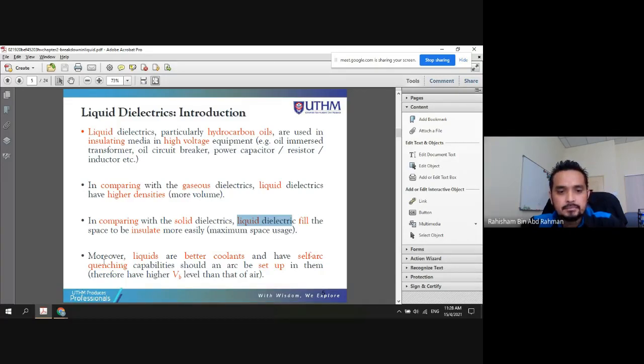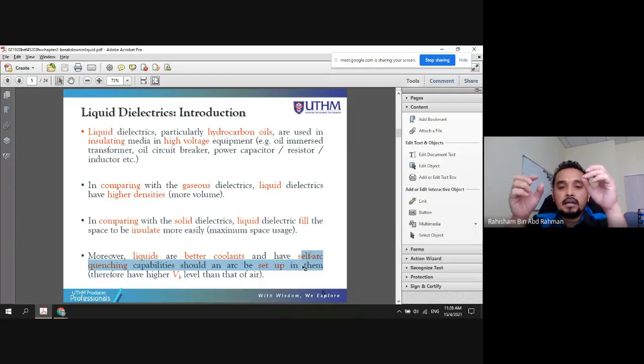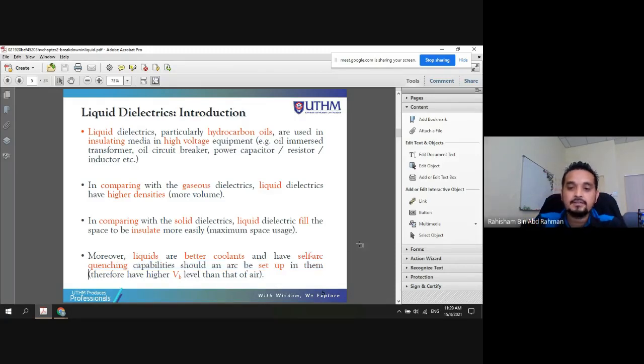For example, we have the liquid. Why do we use liquid? Because it's a better coolant for the transformer, like a cook oil, meaning we need a good cooling system that can have higher density, giving it the property of self arc quenching. Self arc quenching means once we have arc formation, the trigger of discharge, the liquid has the capability to quench, diminish, and remove the arc within the material. Some materials let the arc propagate, but for liquid it will just have the arc and then quench it, so that we don't have breakdown or failure within the material. That is the ideal case.